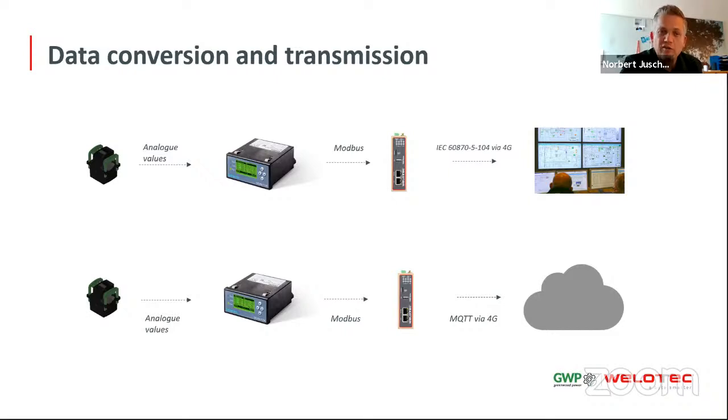It's not digital. The sensor is connected in this case to a Siemens SICAM FCM, a feeder condition monitor, which is also able to detect earth fault directions in isolated, compensated, or low impedance star point grids. This device can also provide the standard power factors, the actual voltage and current levels. With our sensors, this is a closed package, and from the FCM you can make the next step into the chain via Modbus. But now Jos will continue to present this solution.